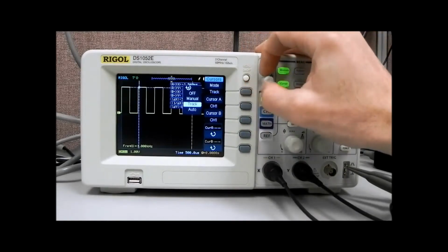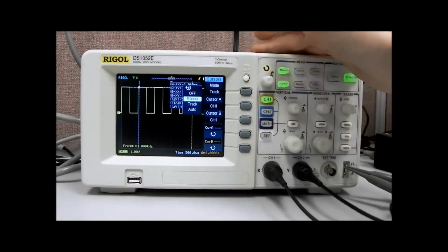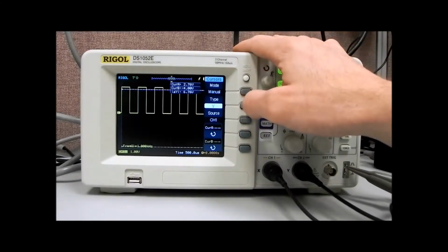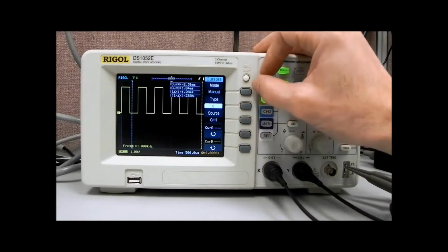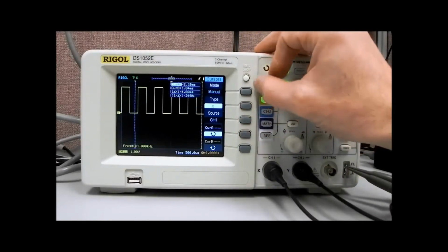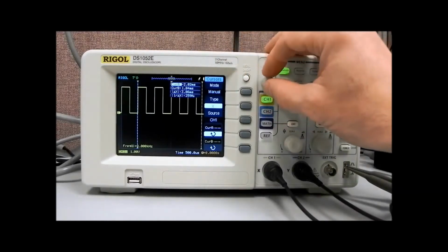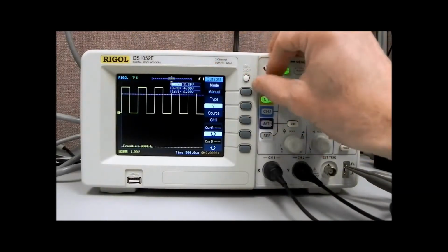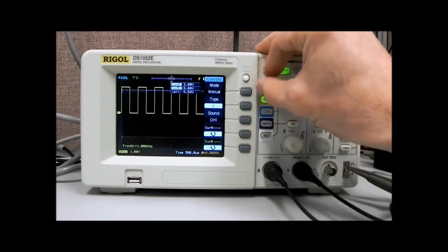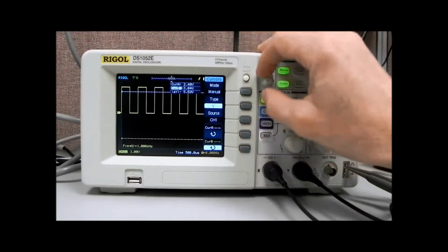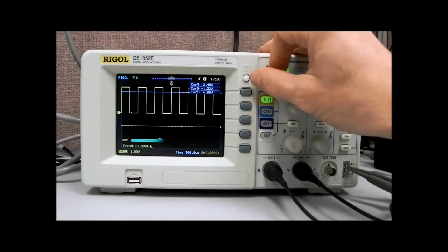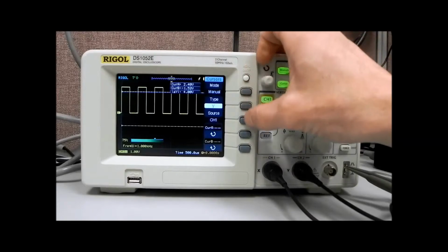If we wanted to do something a little more manual, we can go to the manual mode, and the manual mode is going to allow us to select either Y or the X-axis, and you can see they changed. Let's select A, so we can move cursor A in the X. We can move cursor A in the Y. See that? And we can also move both of them as a delta if we wanted to do fixed, or singly, which can again be useful if you were making some measurements on your waveform.